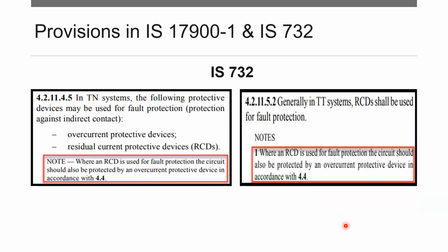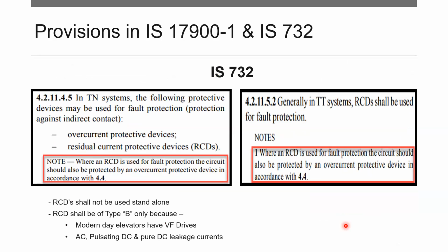Now, it is also important to understand that in TN systems, the OCPD or the MCBs are the primary protective devices. If you want, the additional protection can be offered by the RCDs, but RCDs cannot be used standalone. Similarly, in case of TT systems, RCDs are a must. And if RCDs are used in this system, we cannot use these RCDs in the TT network in standalone condition either. They have to have the overcurrent protective device in place.